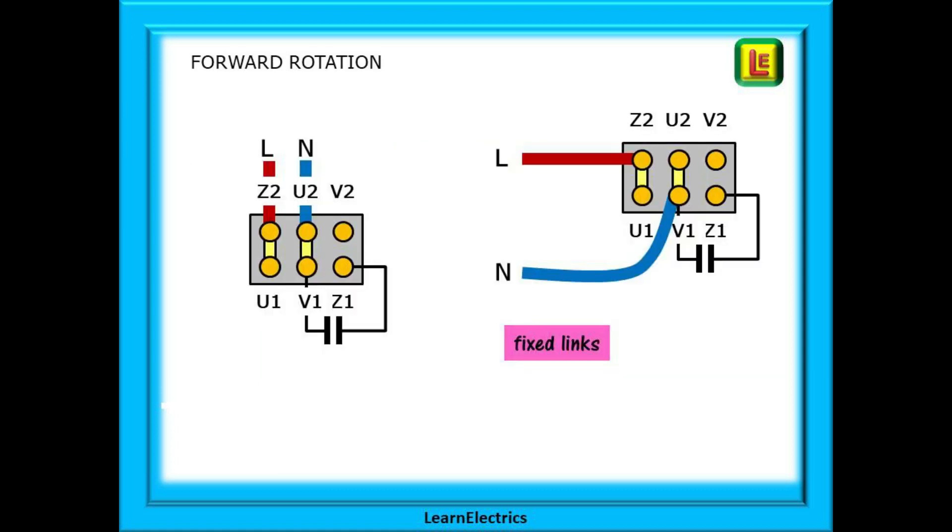You will recall from an earlier video called Single Phase Motors the position of the links on the motor block and these two drawings here show the configuration for forward direction. The only difference between them is the physical position of the neutral cable although this is electrically the same point.